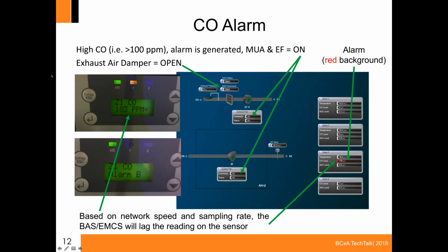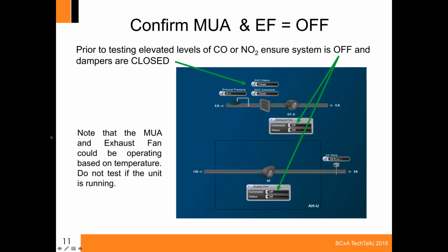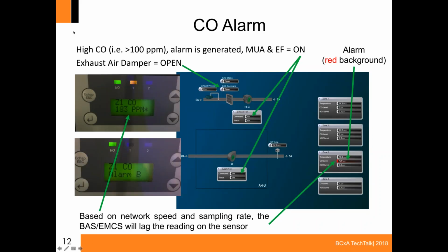So on a CO alarm for testing, you can see here on the left-hand side I have actual snapshots of the gas sensor itself, and then the right-hand side is a screenshot from the Johnson control system that shows that the elevated levels got up to 120 on the BAS, and it did have an alarm. So we got the warning at 25, which does not change color. That activated the makeup air system and all the exhaust fans. And then when it hit above 100, we did get the elevated alarm. You'll notice here that on the left-hand side in the top snapshot, the sensor was actually reading 183 parts per million, and on the BAS graphics, it was only reading 120. This was just due to network lag and a sampling rate. It did eventually elevate up until this level before we turned the gas off so it could switch over to NO2.